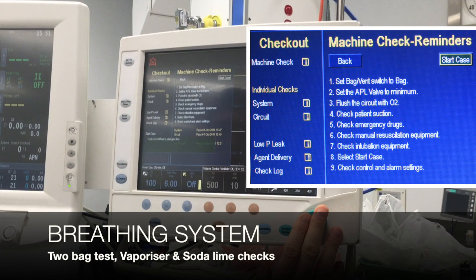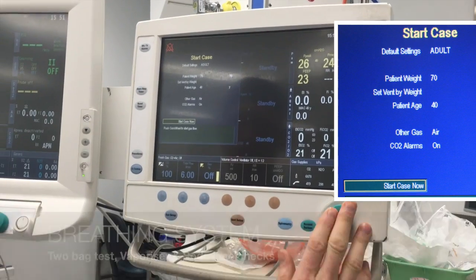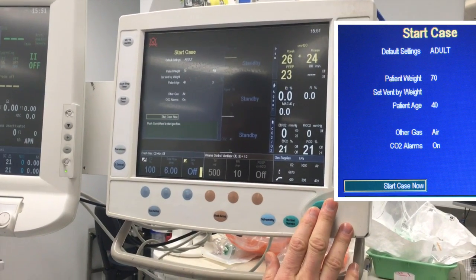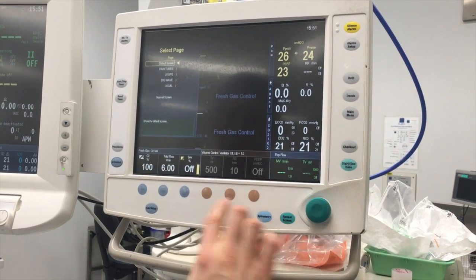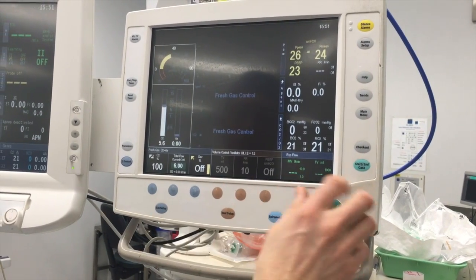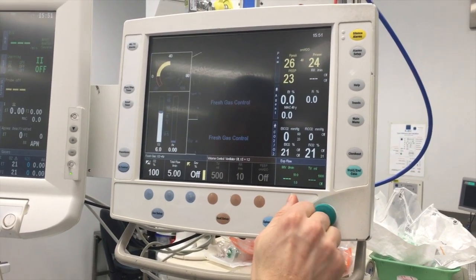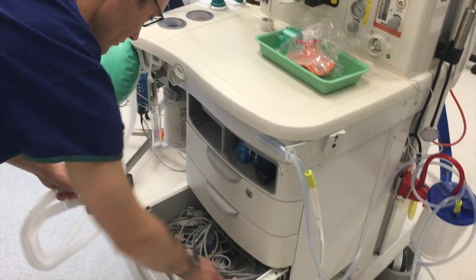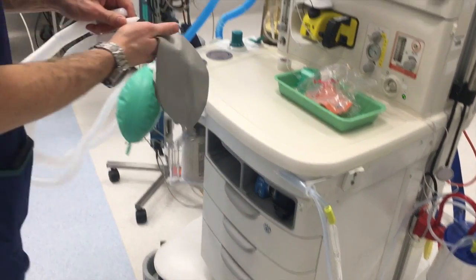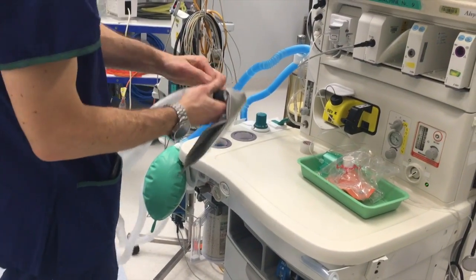After the automatic checks, check the breathing circuit yourself by selecting Start Case and then confirming Start Case Now. This means the machine will start to add fresh gas flow to the circuit. Here I'm selecting 5 litres a minute. Connect a second 2 litre bag to the circuit to perform the 2-bag test.